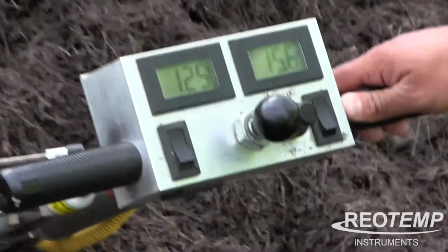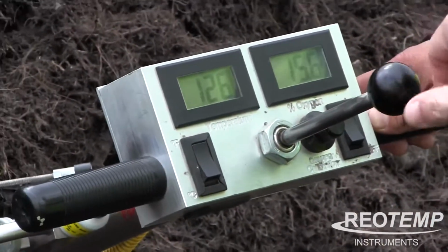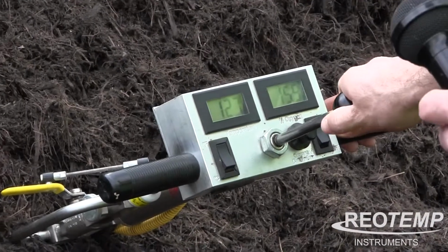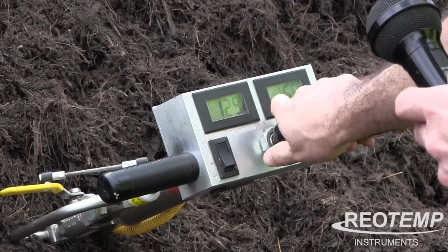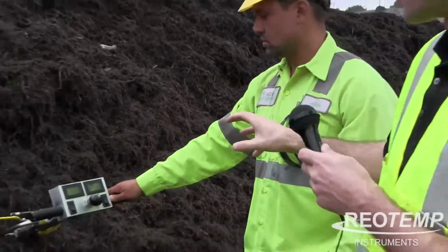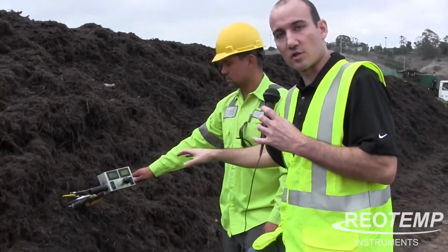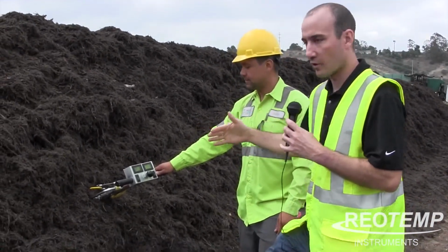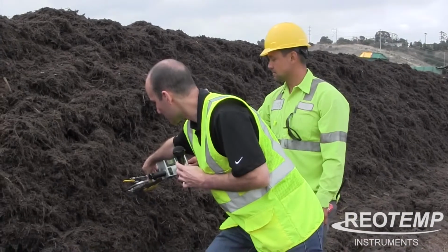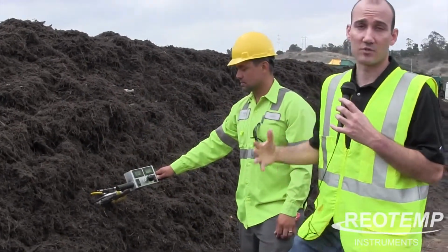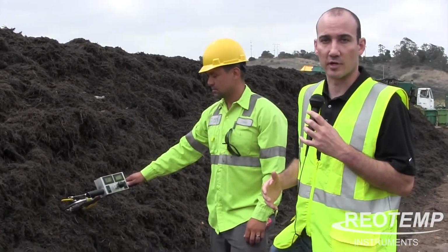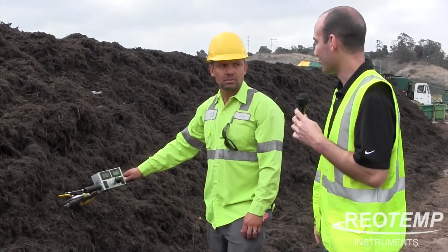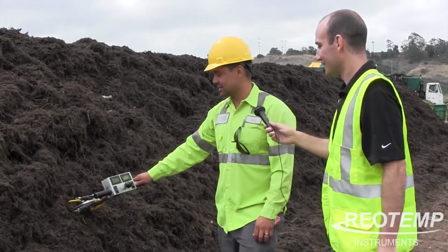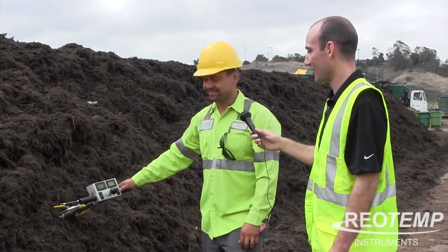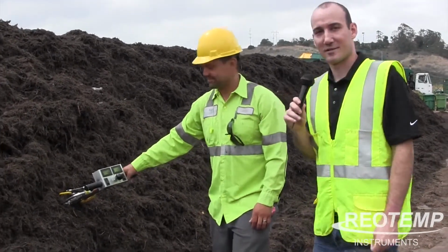As that air moves down and slowly across the sensor, that's when you're going to get that reading. You can see how Alex did a nice job of moving the plunger down slowly, which makes a solid flow of air across this oxygen sensor and then back out. That's what's going to give you your good, accurate oxygen reading. So it looks like you guys have a lot of oxygen in there. Yeah, it's a nice healthy pile. Very nice. All right, well, thanks, Alex.